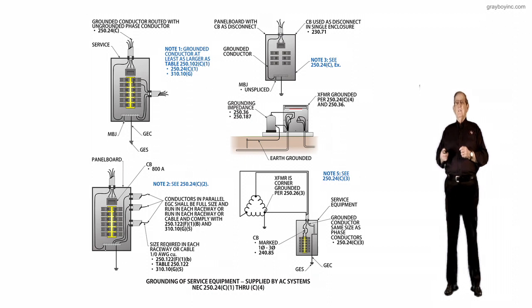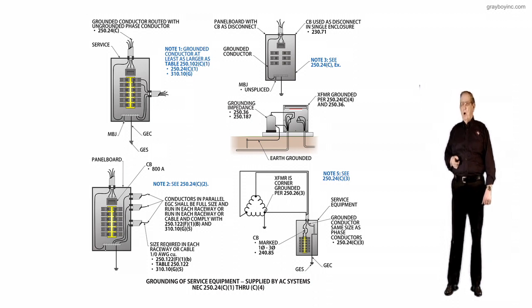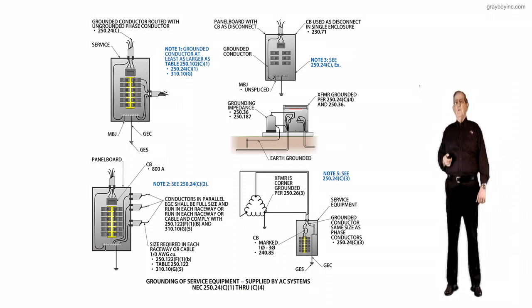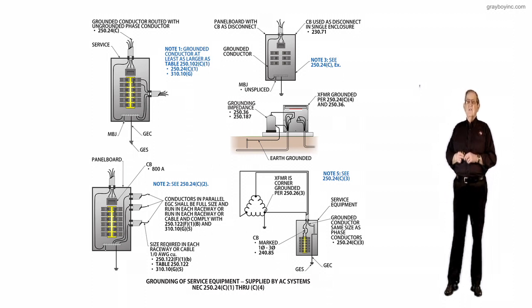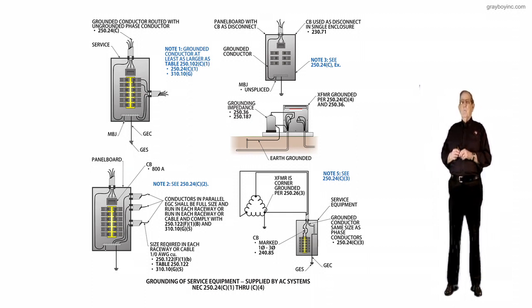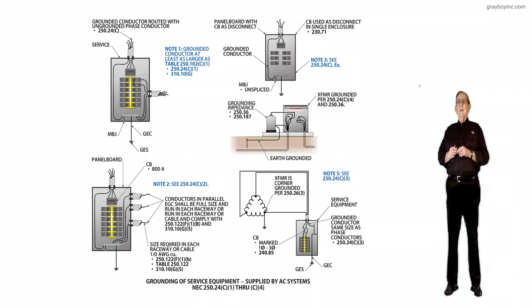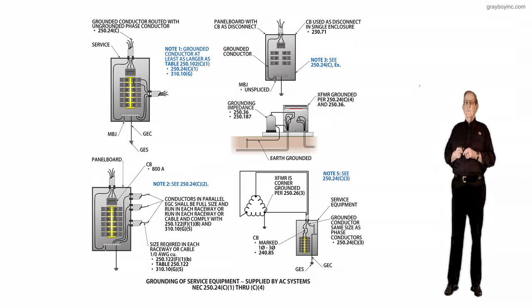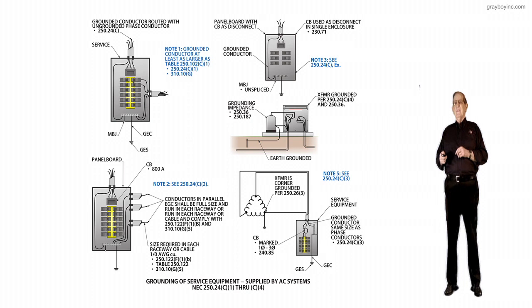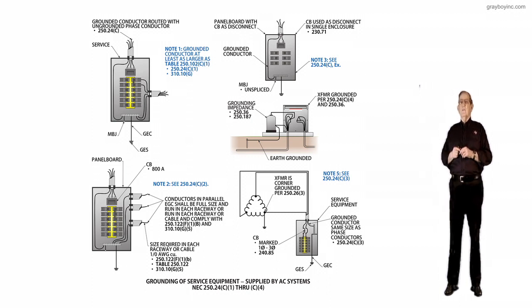Now, lastly, I'd like to look at the transformer to the right and the notes. Now notice we have a corner grounded system. If you look at that transformer, it's a delta corner grounded type system. And then notice that the circuit breaker is a 2-pole that you have there. If we review 240.85, it would have to be marked single phase, 3-phase, not just a regular old two-pole breaker that you might get off of your truck or out of your bins. Then the grounded conductor coming in would be connected just like it was a neutral, so to speak. But the L1, L2, and L3 all have to be the very same size. And you'll find that in 250.24(C)(3): the grounded conductor is the same size as the phase conductors, a little callout that you see there.